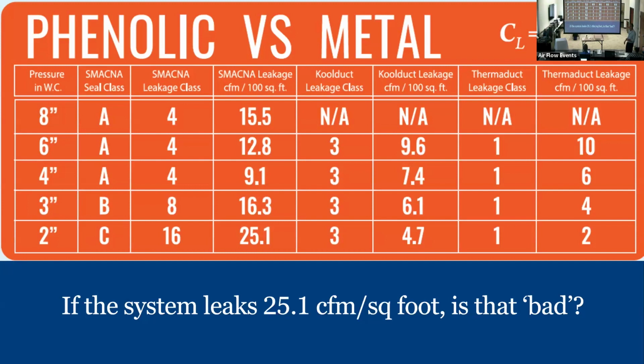Now notice, everything that's high pressure is called seal class A, and we're going to talk about what that means. As the pressure gets lower, we change the seal class. At 4 inches of pressure, we are allowed to leak 9.1 CFM per 100 square feet, which doesn't sound like a lot. But your system may have more than 100 square feet of duct. This is not linear feet of duct, this is the square footage of the perimeter of the duct. Now notice, when we get into the low pressure duct, it's like you can leak all you want. We can leak three or 2.5 times as much.